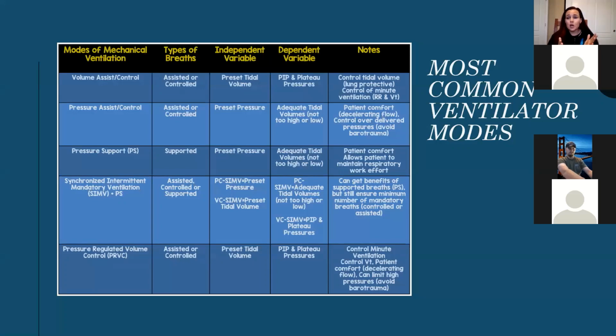So what you need to know is what yours is called on your ventilator. Some of them are simply called volume control. Then you're going to have an option to do SIMV, which is synchronized intermittent mandatory ventilation, which is also a volume mode. PRVC, pressure regulated volume control, is also a volume control mode. So all these ventilator companies just take it up a notch and make it a little more confusing, but you just need to break it down. Are you controlling volume or are you controlling pressure? And if you're controlling one, the other one's going to vary. That's what you need to pay attention to.